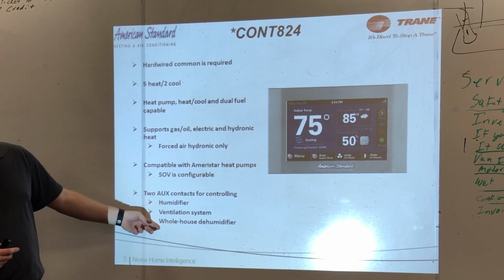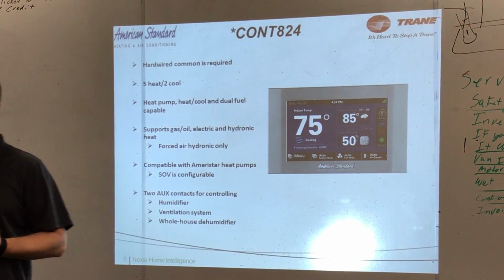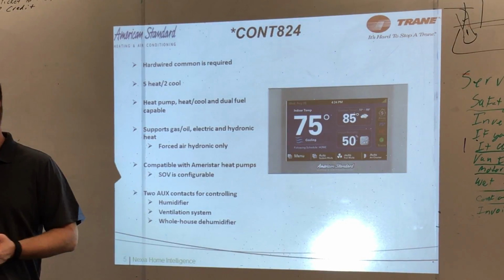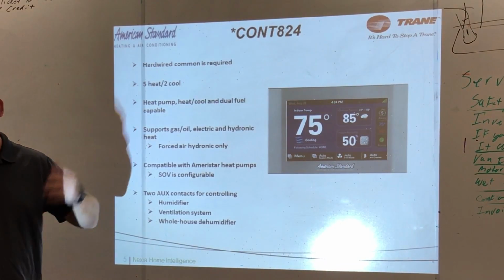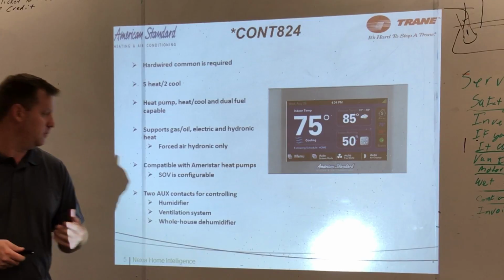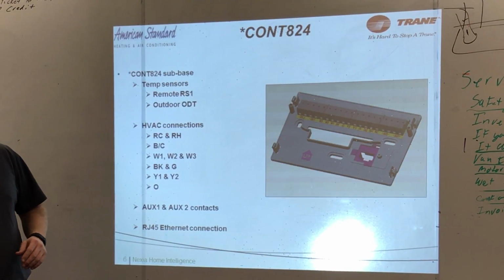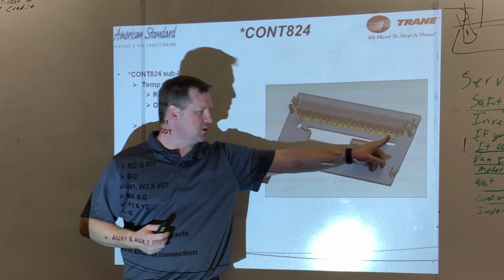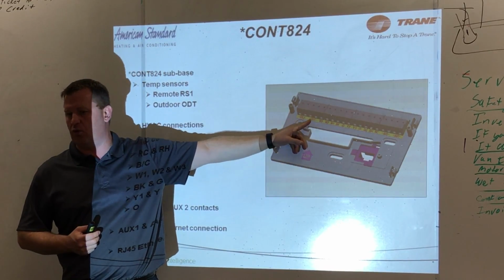You have 2 sets of auxiliary contacts, so you can control a humidifier, ventilation, or a dehumidifier, which we don't really do here, but the capability is there. This is a full wiring stat, 24 volt.